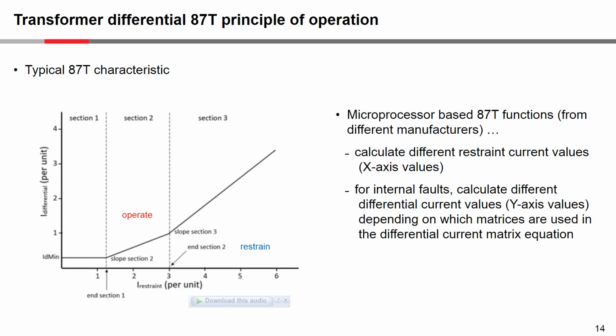And so now you have two relays calculating restraint and differential quantities differently, and then they apply them to a characteristic. And of course, if the point is above the characteristic, that would be in the operate region, and if the point is below the characteristic, that would be in the restraint region.